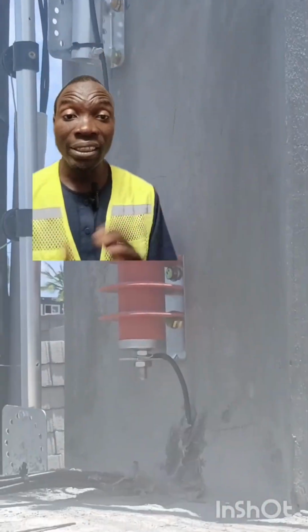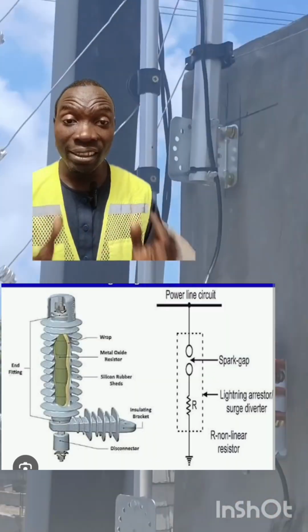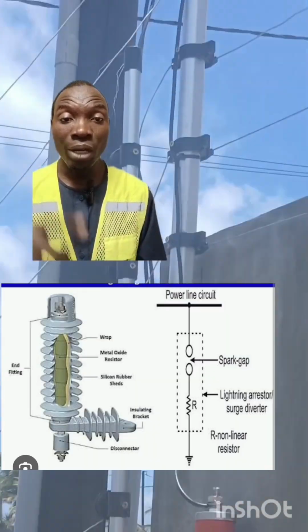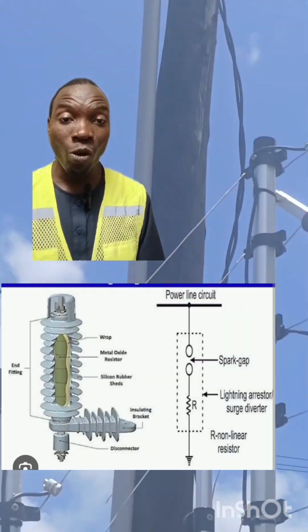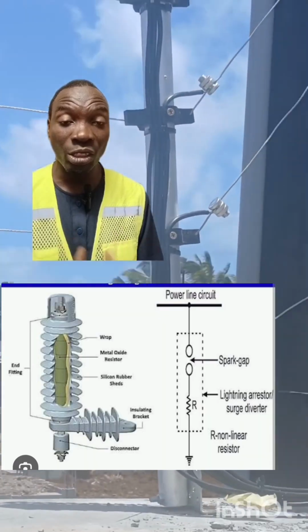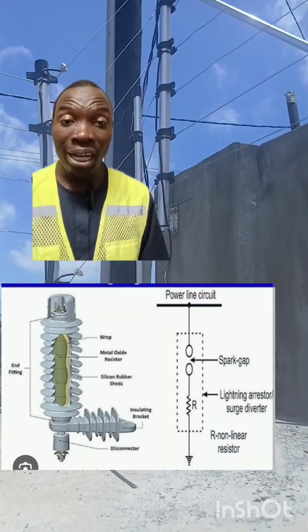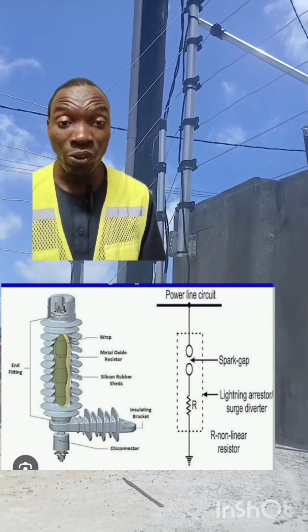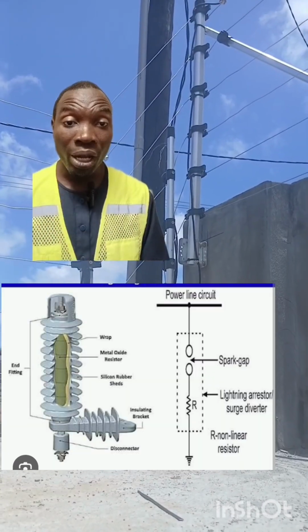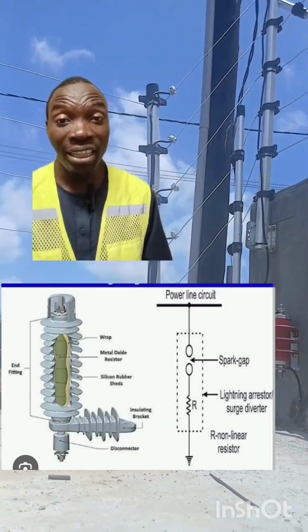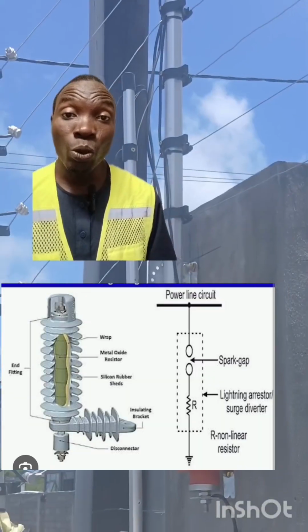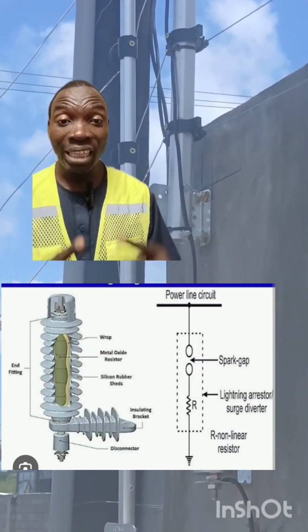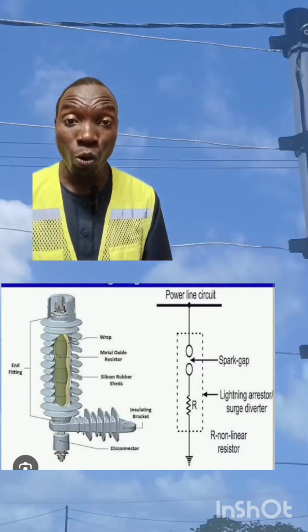How does a lightning arrestor work? It is designed with two terminals, an upper terminal and a lower terminal, just as you see on your screen. Those two terminals are not electrically continuous - if you place a probe at the upper and lower terminal, there will be no continuity because there is an air gap between them.